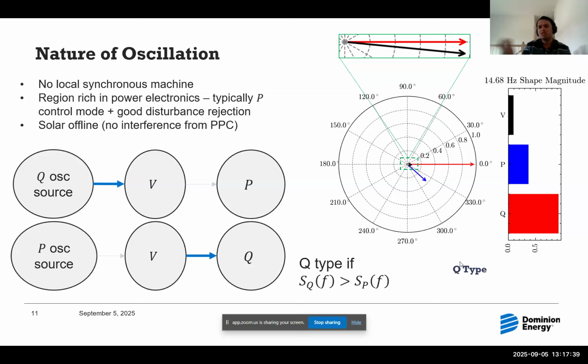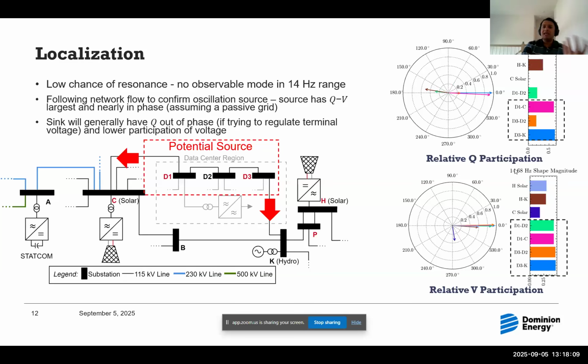In this region, there is no device that will lead to that. So if you start with a voltage oscillation in this region, there is no neighboring device that might turn it into a megawatt oscillation also. So in this case, what you'll see is that it's predominantly a VAR type of problem, and that's why it's mainly seen in voltages and VAR, and not so much in megawatt consumption of this particular data center load. So volt-VAR kind of issues. And that tells us what to chase when we are trying to localize.